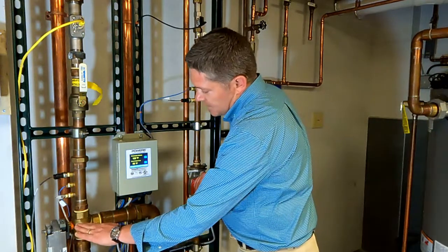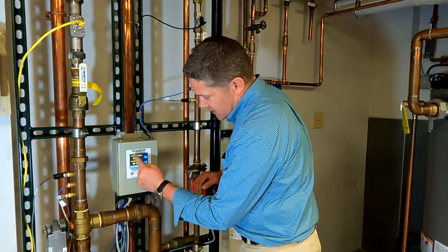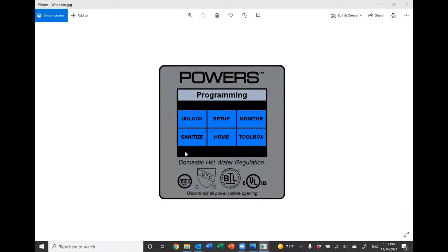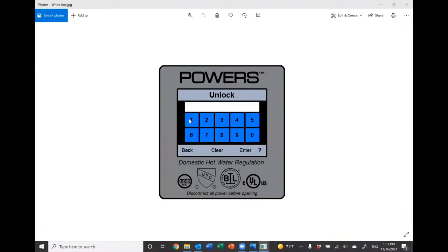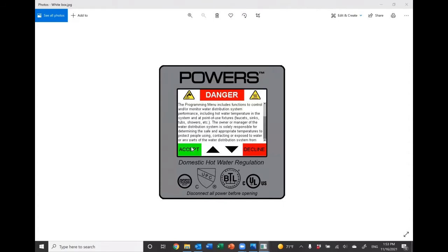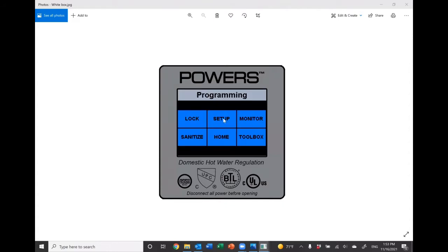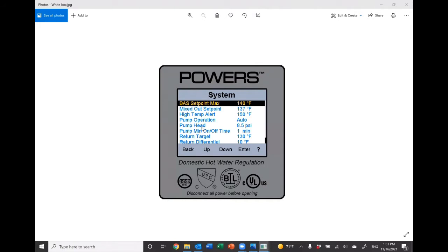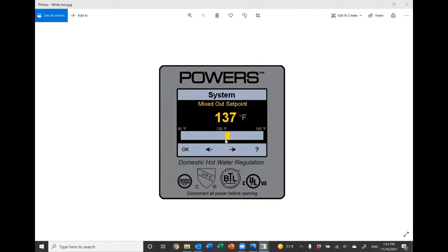As far as setting this thing, you hit the program, you unlock, put in your password, enter, accept, setup, system, and then you would go to that mix set point, hit enter. There's a touch screen here with a sliding scale that you can just dial it in, or you can use the arrows to change 1 degree at a time. And dial in, in this case I got it at 125, okay, that's set up.